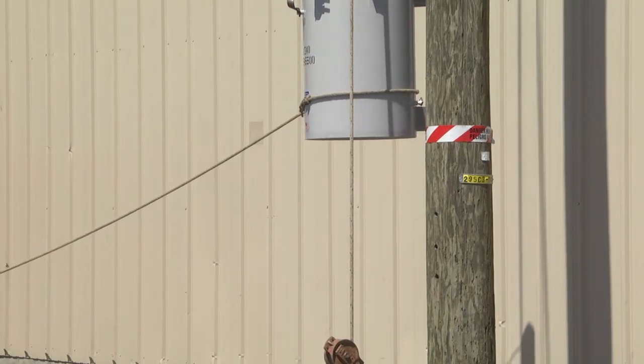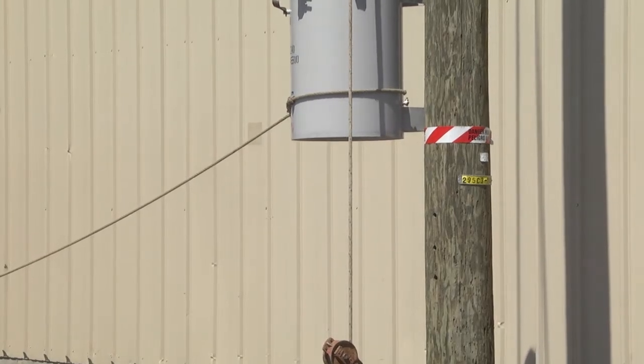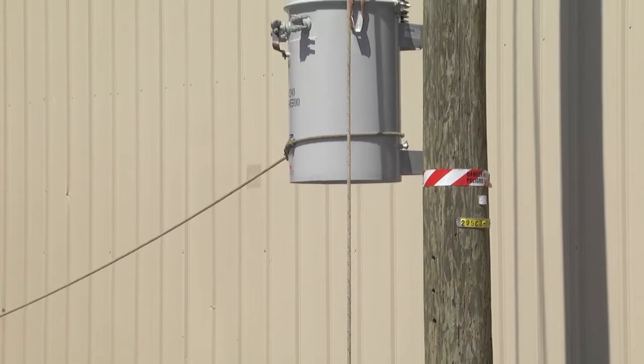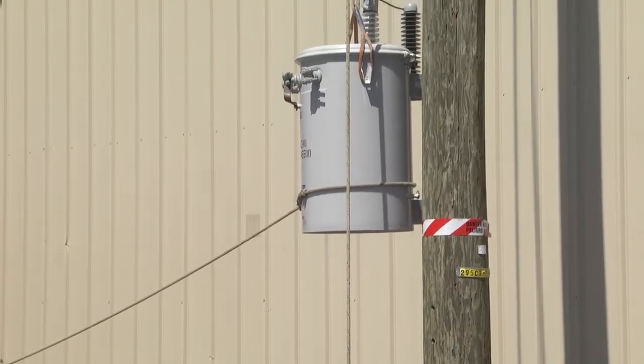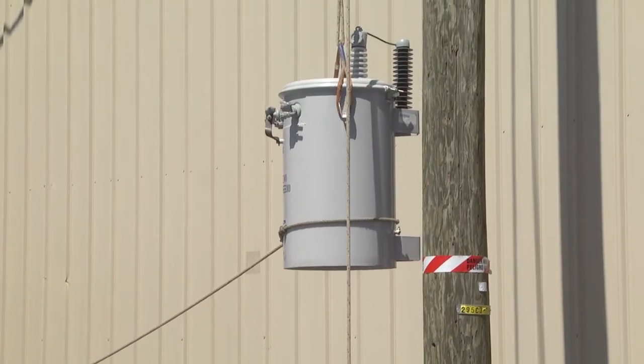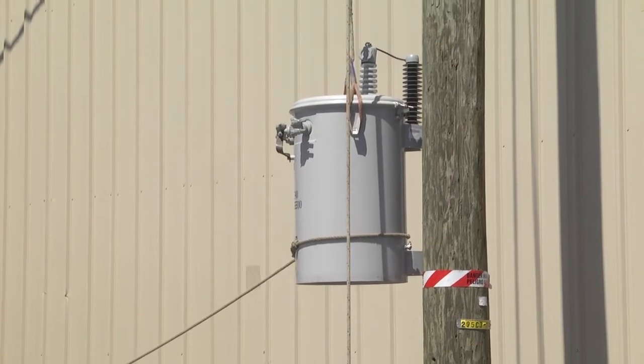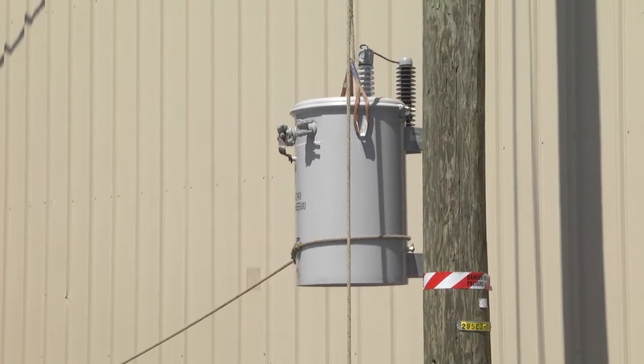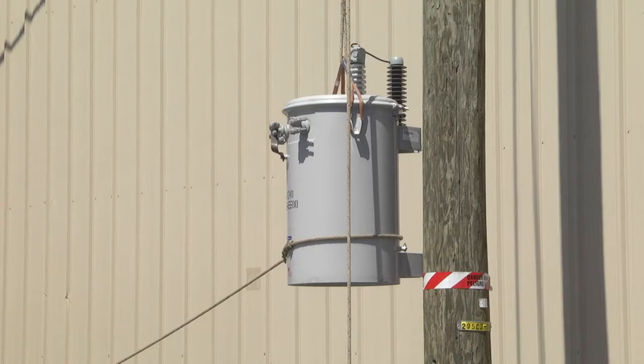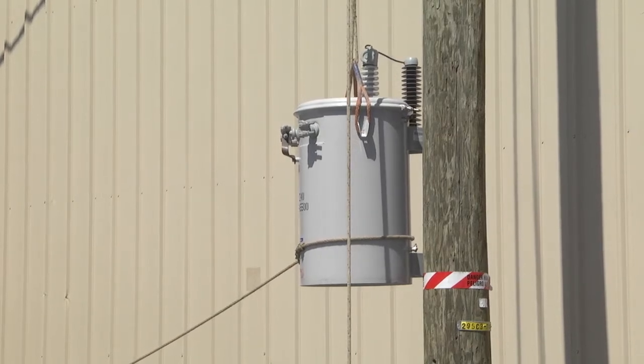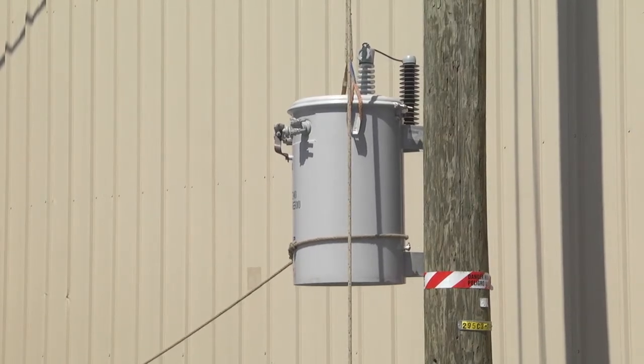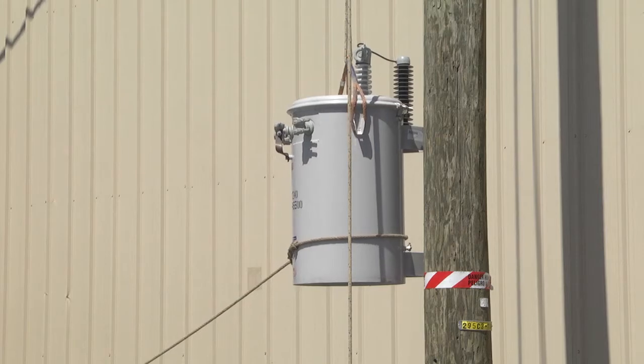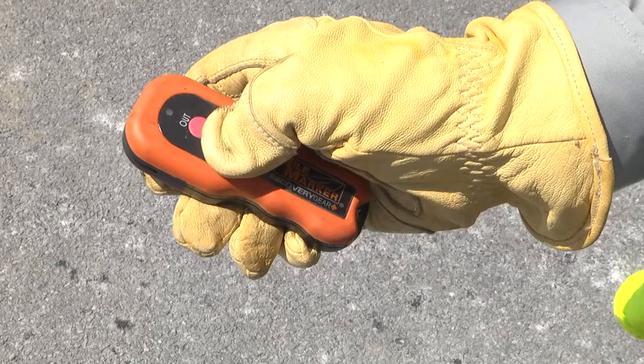There we are in a hold position. As you can see, the transformer is not creeping down in any way. This is where you can properly secure the transformer once it's at the designated height needed. The only way the transformer can be moved at this time is by use of the winch controller.